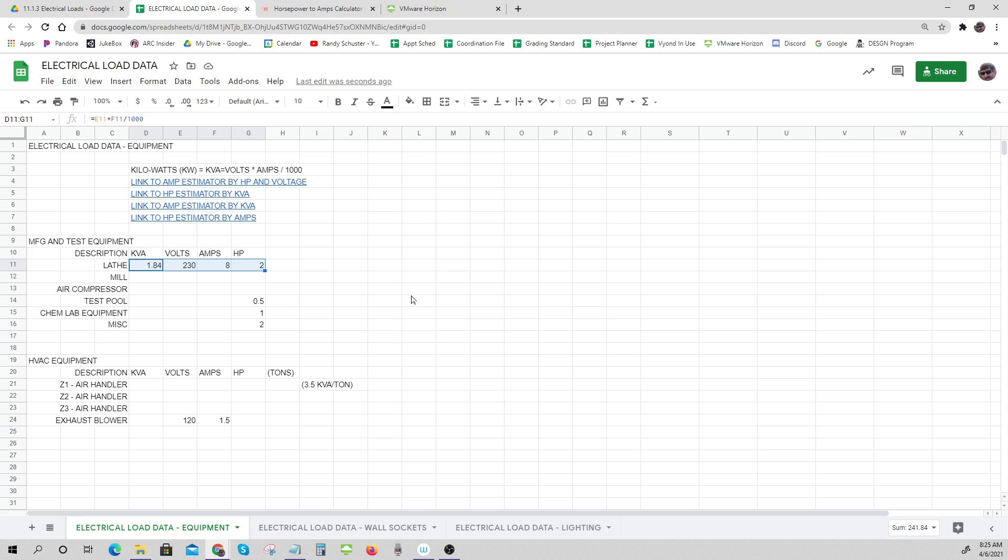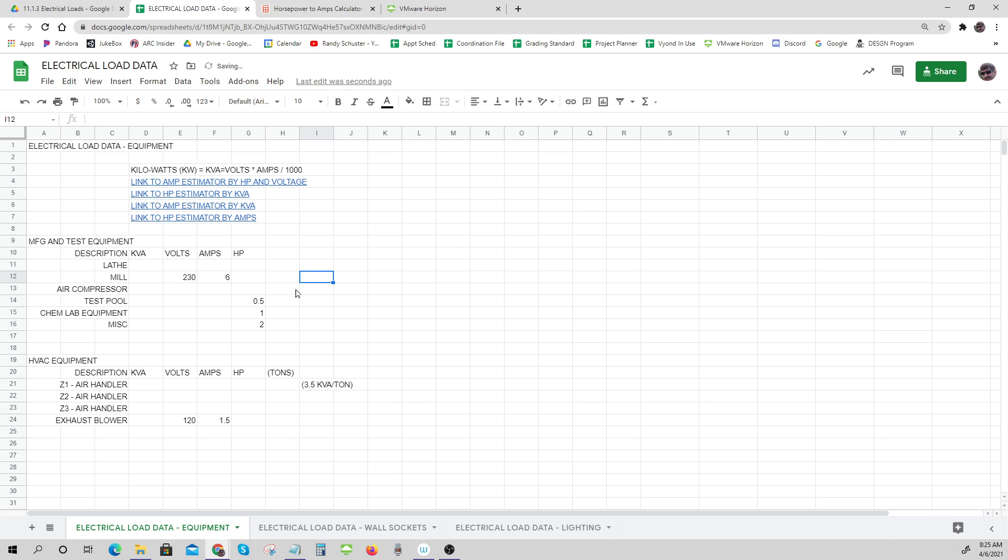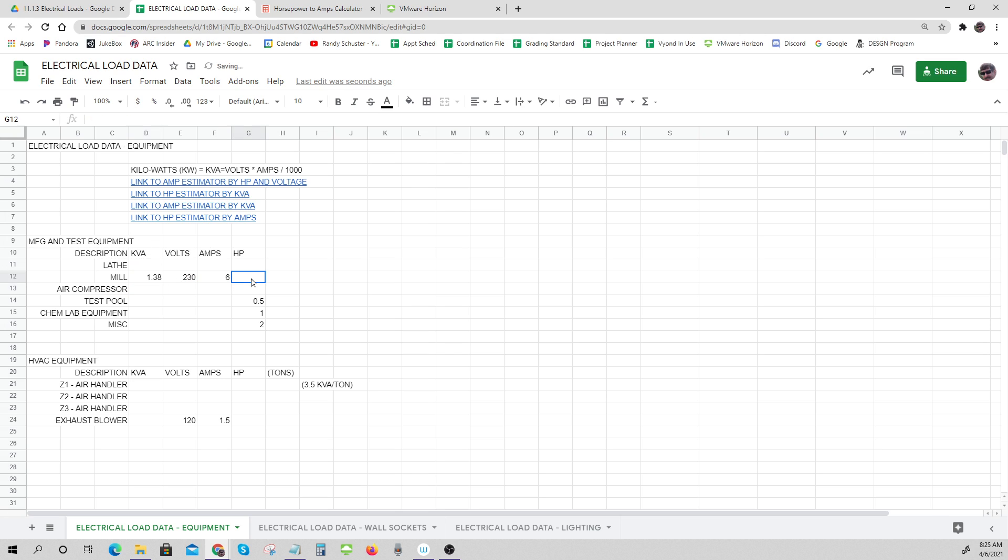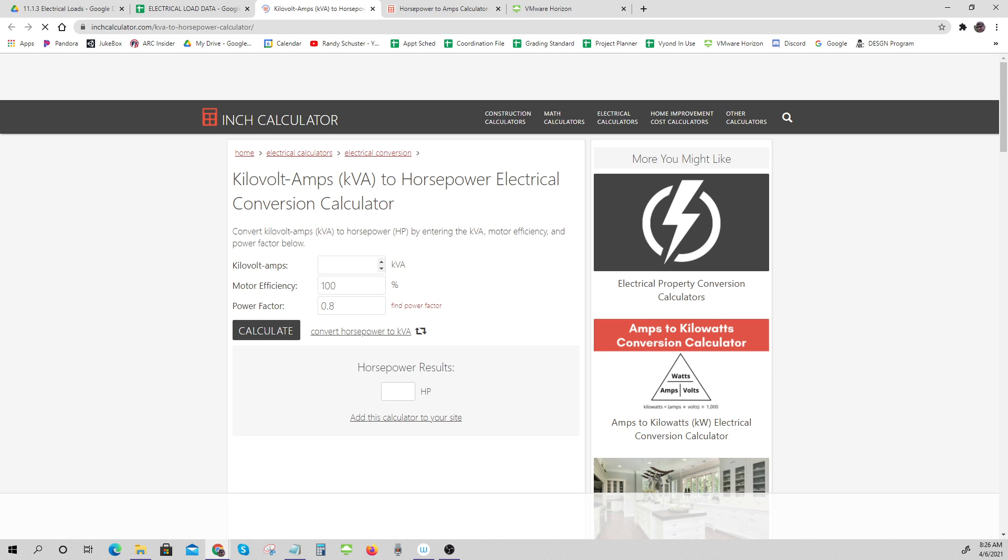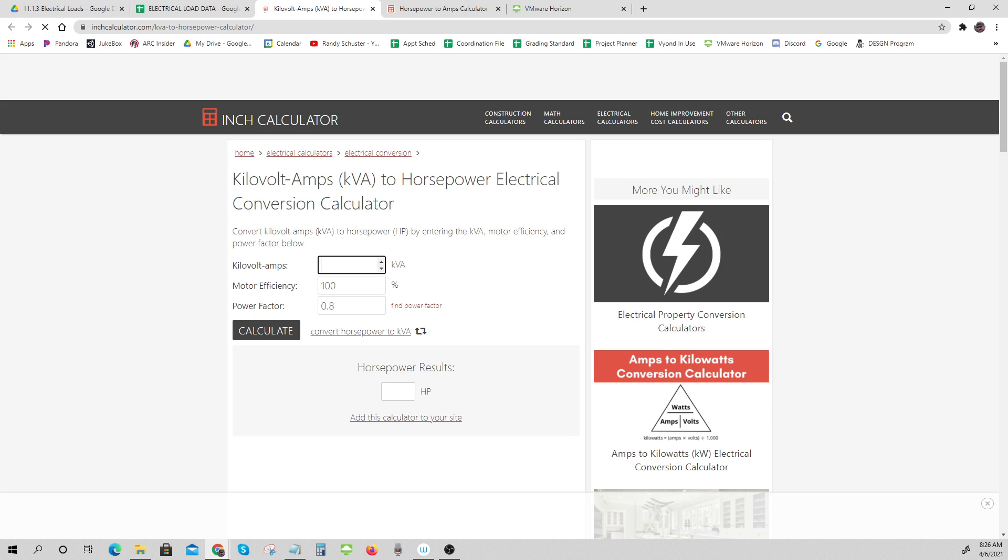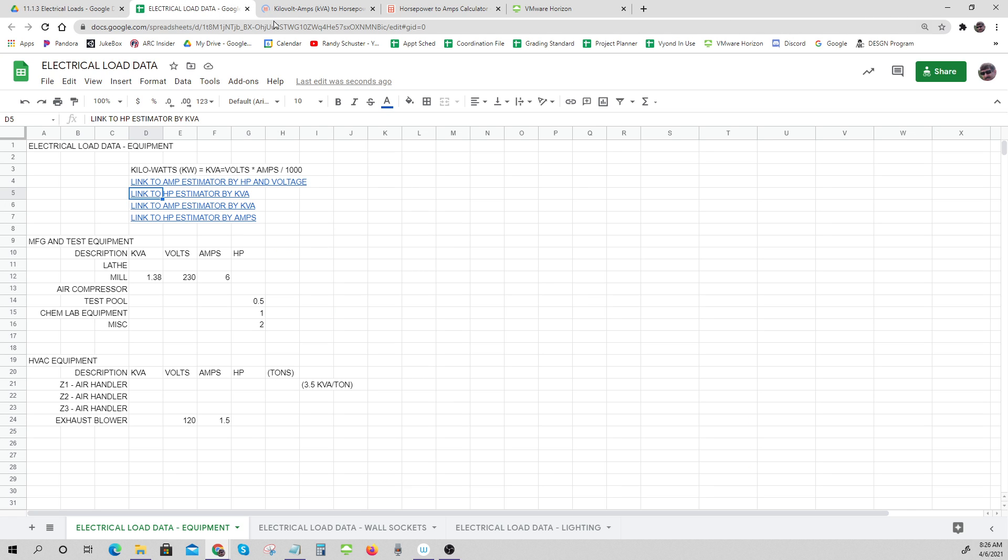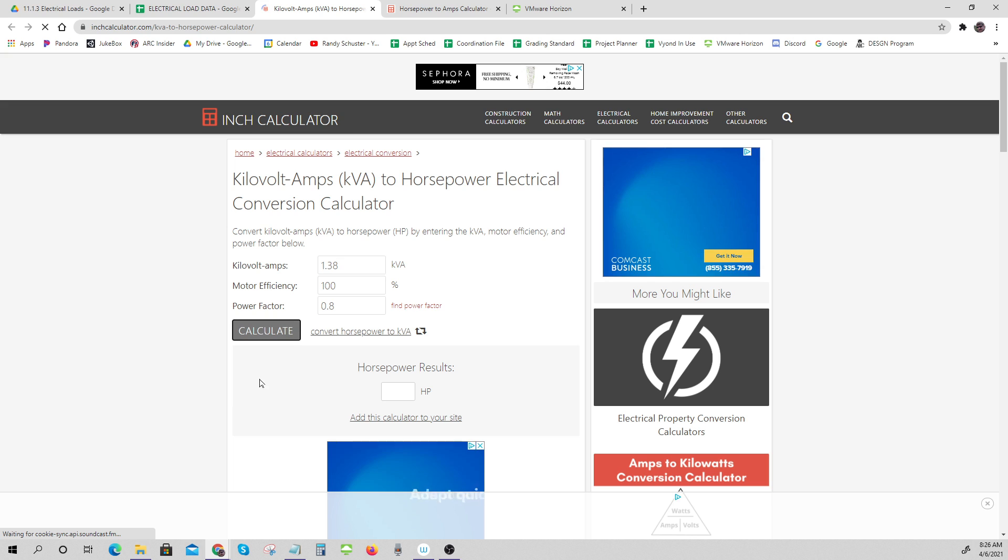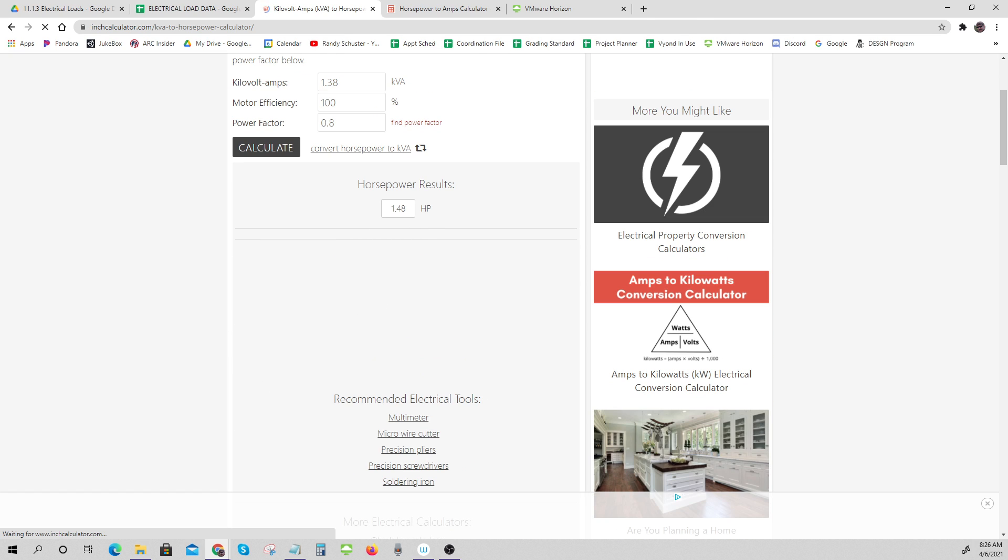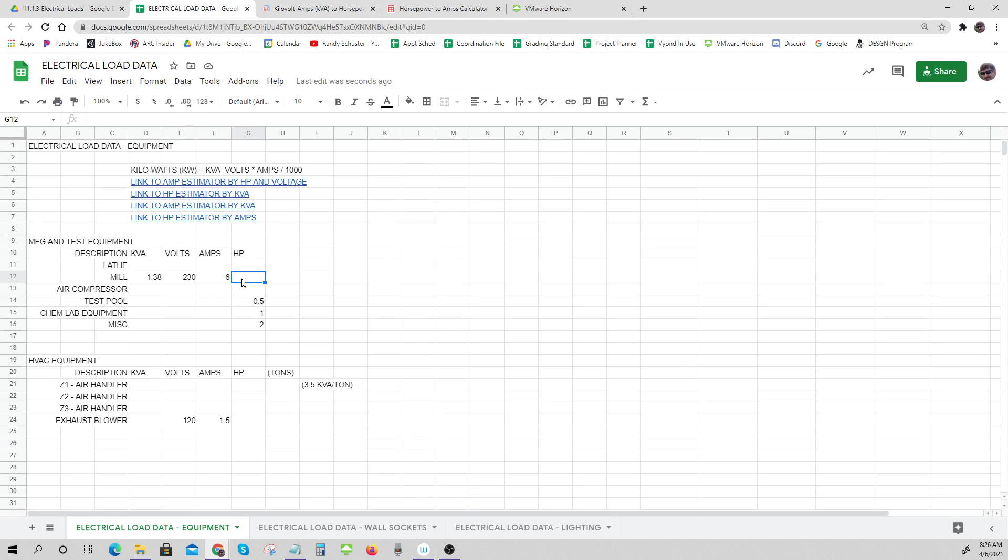Now it might turn out that I learned something else. Maybe I know that my mill is 230 volts with six amps, so I have kVA: it equals volts times amps divided by a thousand. But I want to know how many horsepower that is to finish filling this out. Here's horsepower - oh look at that, kilovolt amps. What did I say it was? 1.38. Calculate - that's about 1.5, 1.48, 1.5 horsepower motor on the mill.